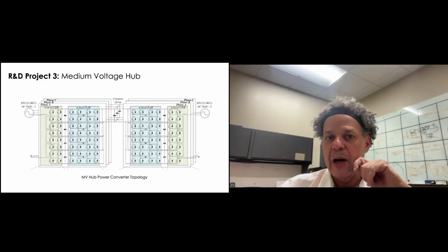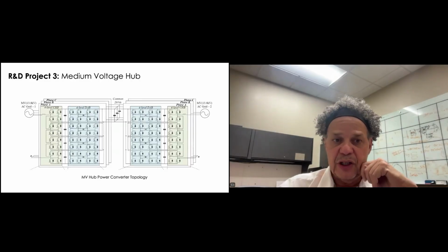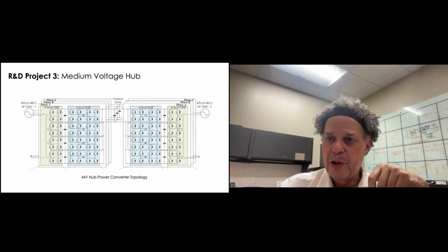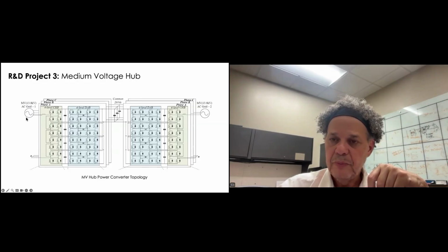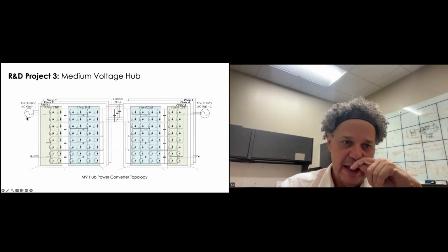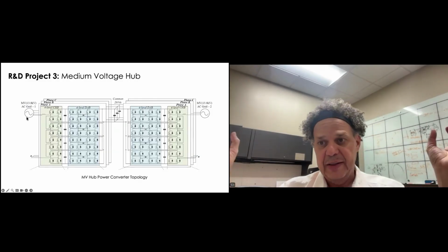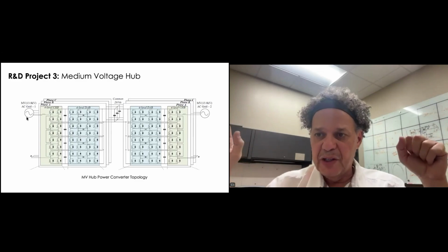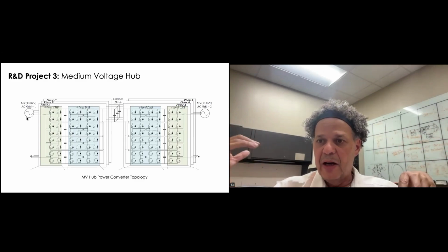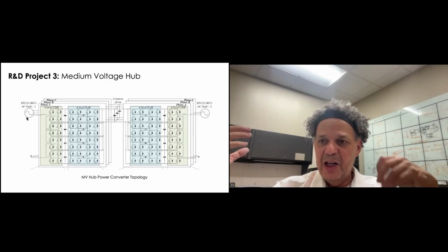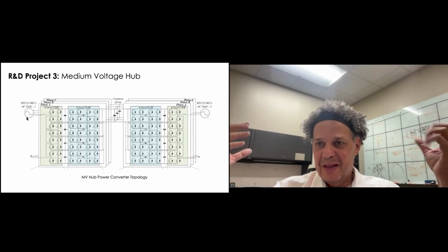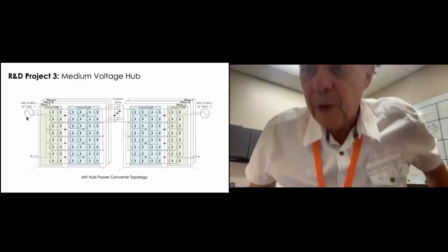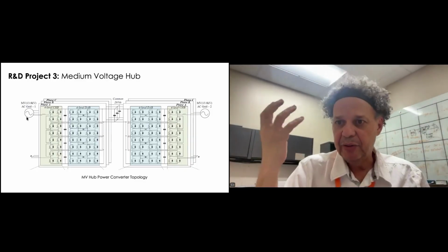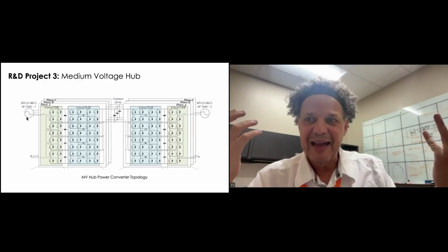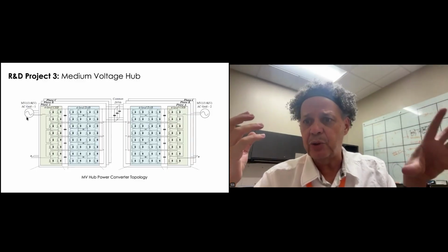Another project is what we call the medium voltage hub. Consider, for example, you have two AC feeders - one is 13.8 on one side and another 13.8 on the other side. So we have two feeders, and one, for example, has a lot of load, and the other is very lightly loaded. If you have a very heavy load, you're going to compromise the operation of that heavily loaded feeder. And at the same time, the light feeder is just sitting there, not doing any job.